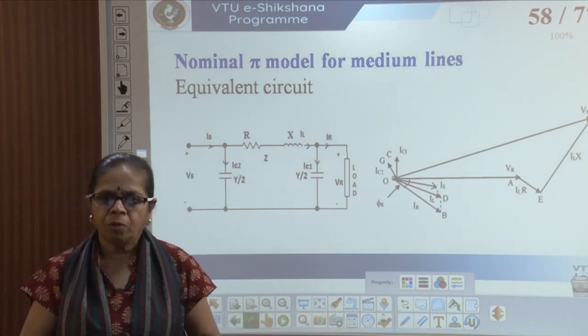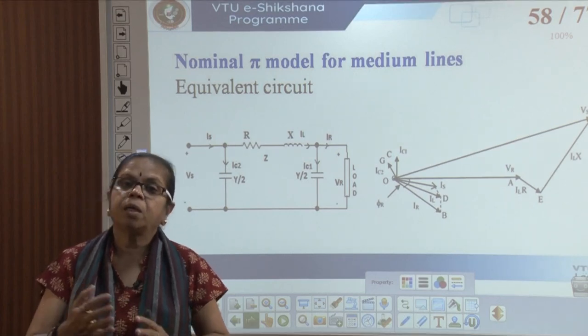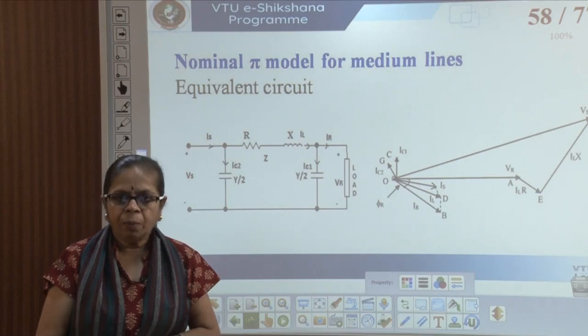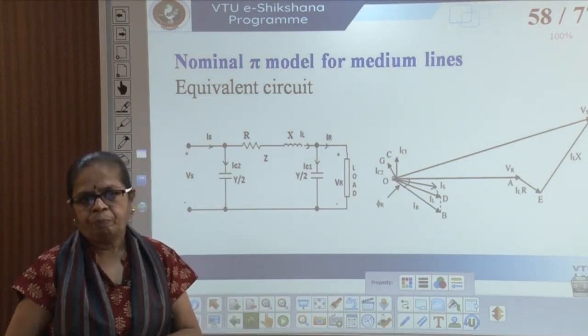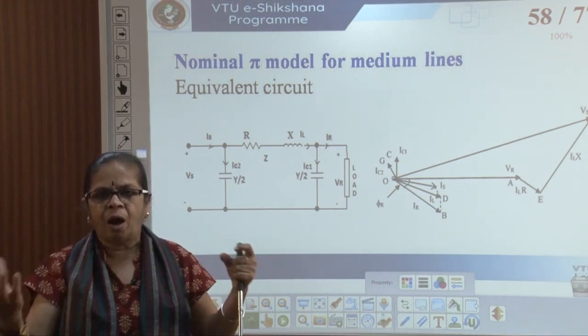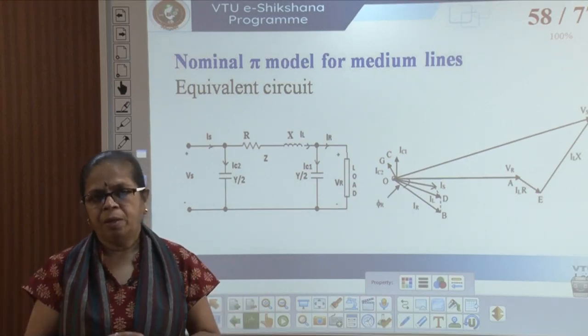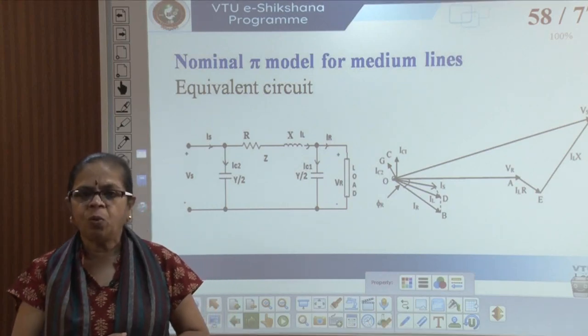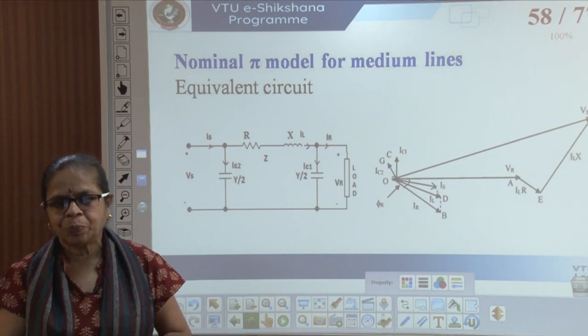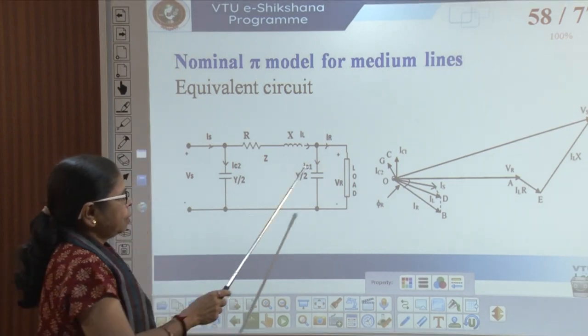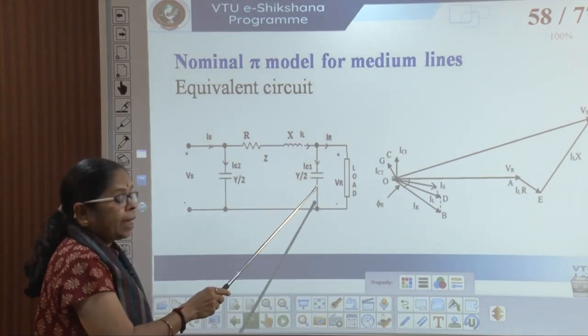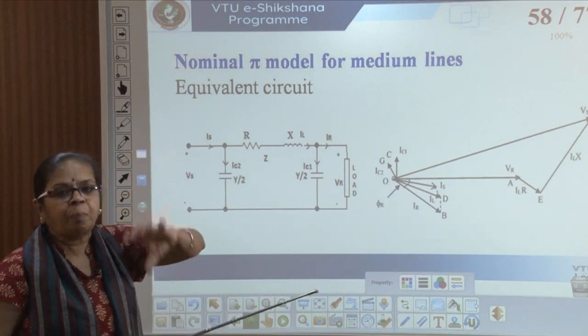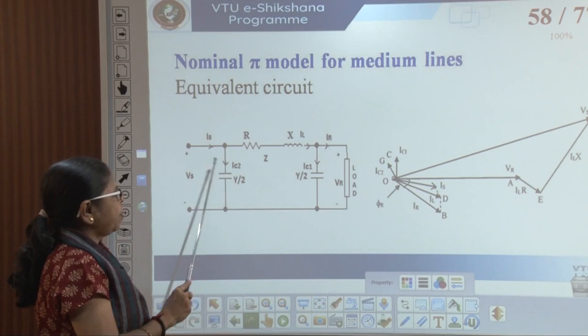Now let's move on and see the nominal pi model for medium lines — this is another circuit model. In the pi model, the impedance of the line is lumped together and the admittance is split into two halves: half at the sending end and half at the receiving end. This is called the half-line charging admittance — 'half' because you are taking half the value, 'line charging' because it is due to the capacitance.